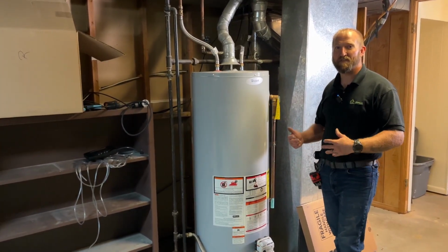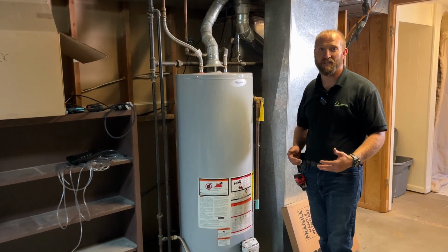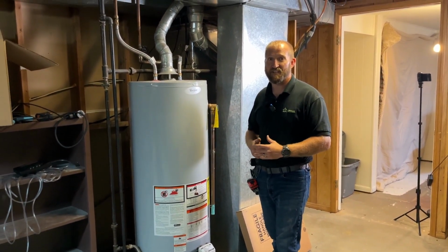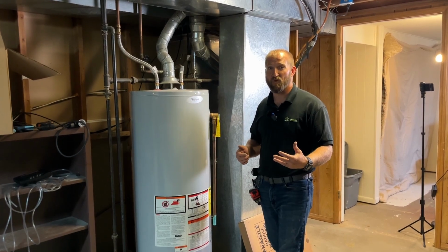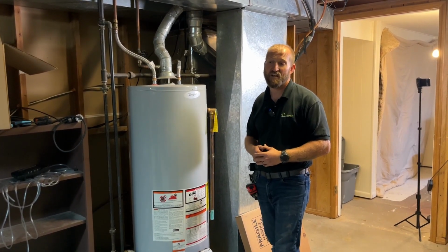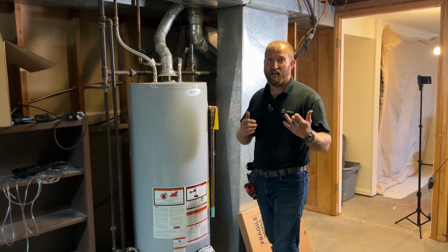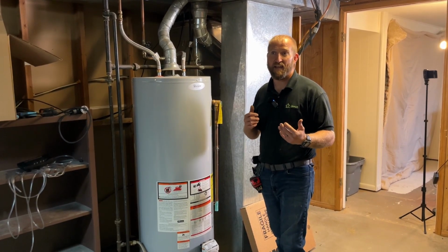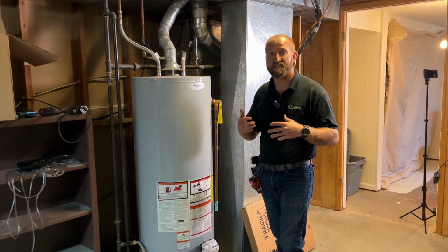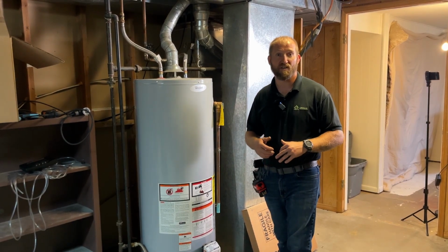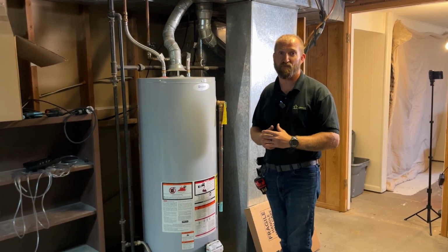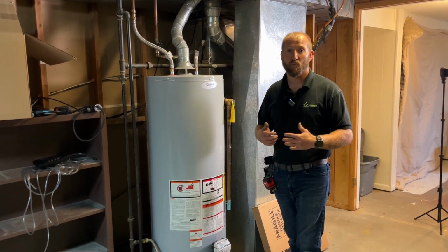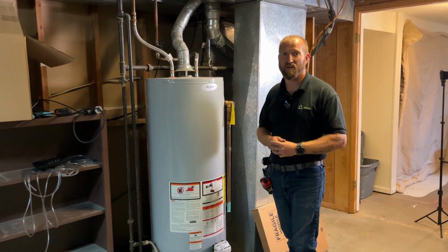So now that we've identified all the different components on the water heater and the furnace and the ages and conditions of them, we're going to set up for the worst case depressurization test. That's going to include getting a baseline reading with a manometer, and then turning on all of the bath fans, the dryer, anything that exhausts to the outside. Like I said before, the recirculation fan above the range, we're not going to have to turn on because that's not exhausting to the outside.